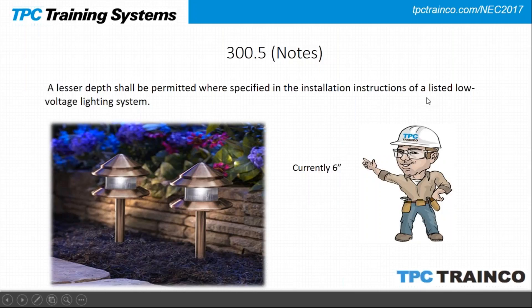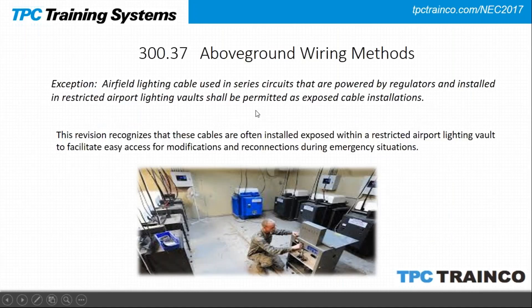Section 300.37 on above-ground wiring methods addresses airfield lighting. A new exception states that airfield lighting cable used in series circuits powered by regulators, installed in restricted airport lighting vaults, is permitted to be exposed. Most of this wiring was probably already exposed, so this exception now provides code coverage for that practice.